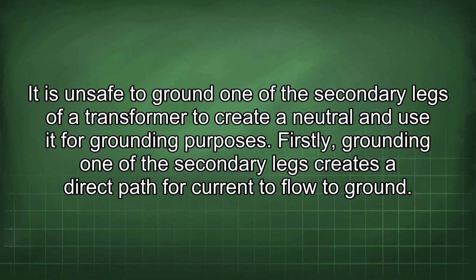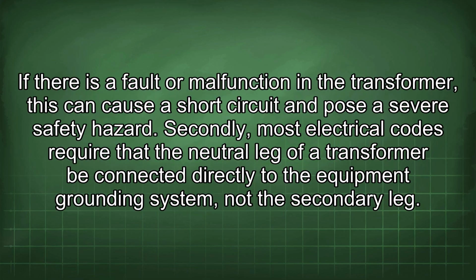It is unsafe to ground one of the secondary legs of a transformer to create a neutral and use it for grounding purposes. Firstly, grounding one of the secondary legs creates a direct path for current to flow to ground. If there is a fault or malfunction in the transformer, this can cause a short circuit and pose a severe safety hazard. Secondly, most electrical codes require that the neutral leg of a transformer be connected directly to the equipment grounding system, not the secondary leg.